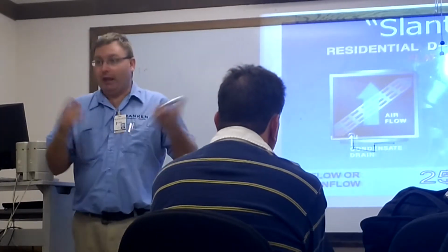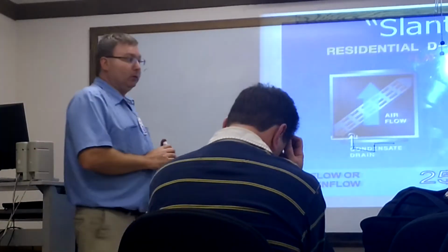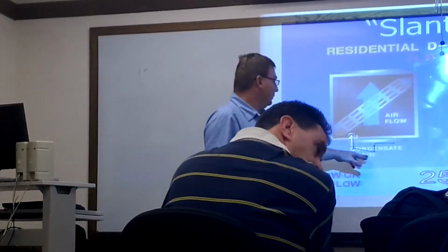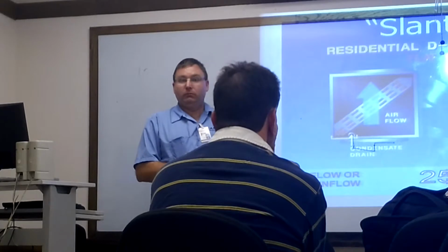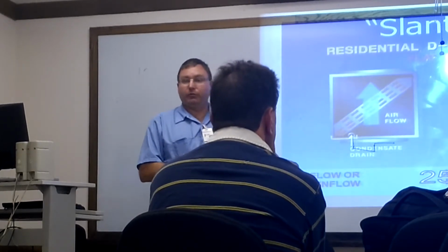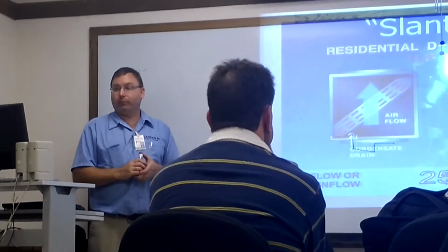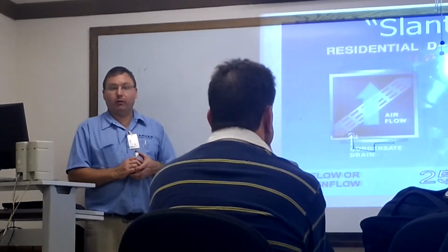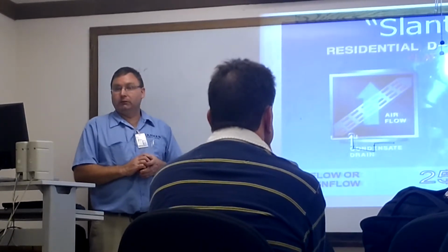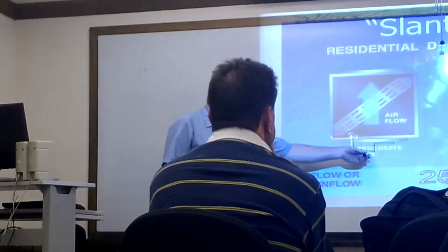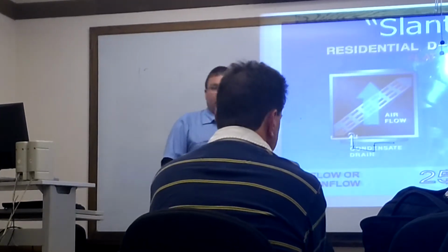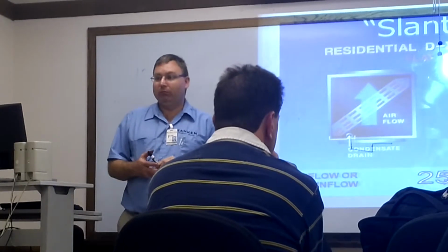Check them traps. In the winter we don't have to check the traps, but in the summertime, when you go to the air conditioning startups, you want to make sure you check the traps. In refrigeration, if you've got one that's not draining and leaking water all over the place, or icicles hanging below the evaporator coil, check the traps if it's got one on it. It might be that the heat tape on your condensate trap is bad and the drain froze up.